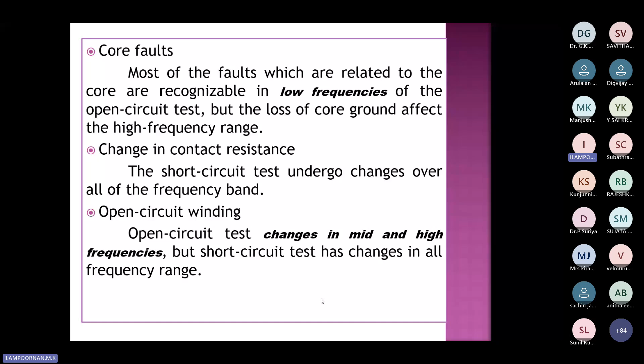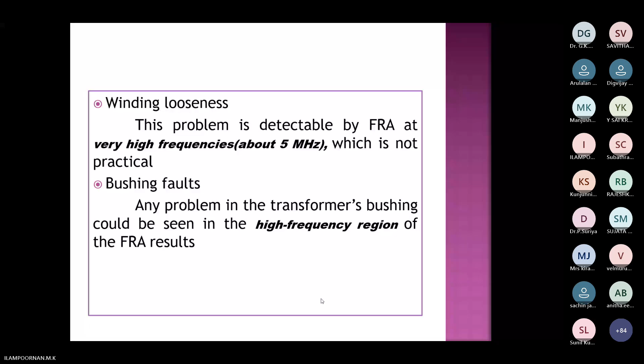There will be looseness. That means the bolt tightness is maintained by the spacers. If there is any problem in the spacers, that can also be identified. It will be visible in the high frequency, up to 5 megahertz. And there will be bushing faults. Of course, we will have them in the high frequency. It will be seen. And we'll come to the end.